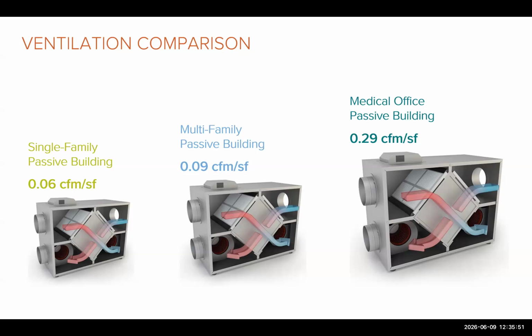High ventilation buildings, such as hospitals and labs, are ventilated at rates above 0.5 CFM per square foot. Figuring out if you're a high ventilation building is a critical issue for both energy usage and project compliance with Phius targets. So that was one of the first things we had to look at the beginning of the project.